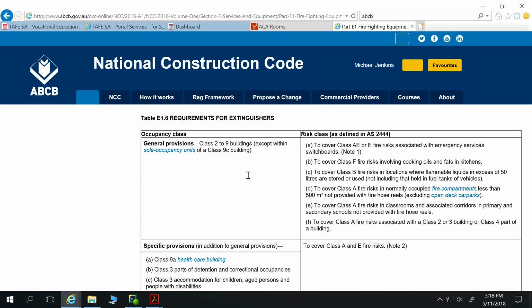So, to cover Class B fire risks in locations where flammable liquids in excess of 50 litres are stored or used. Listen to that one, because if you've got a car show, did you use yours for a car showroom as well? Right. Okay. So both of you. Oh, hang on. Oh, there we go. No, we've got an exit. Not including that held in fuel tanks of vehicles. So, cover Class B fire risk in locations where flammable liquids in excess of 50 litres are stored, but not including that held in fuel tanks of vehicles. Well, possibly we don't need them there. We're not going to be refueling vehicles in that showroom.